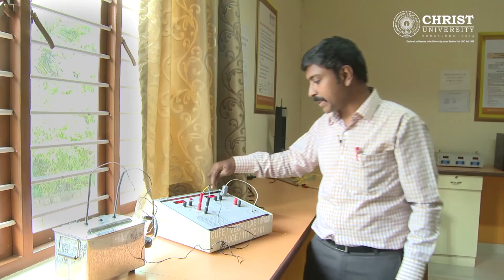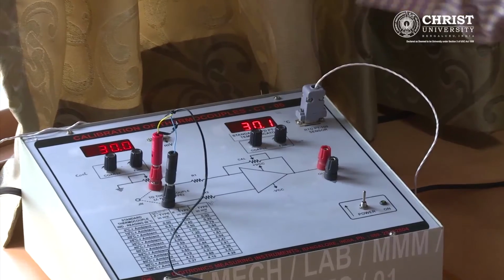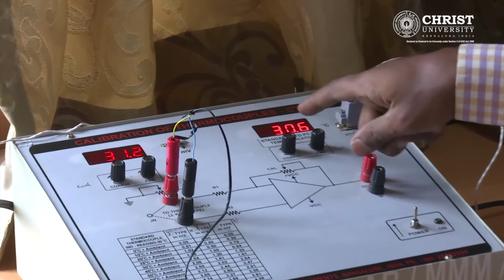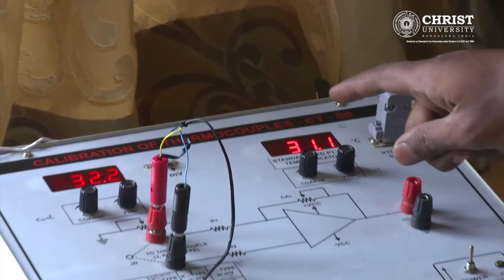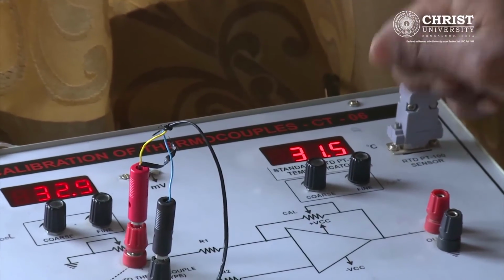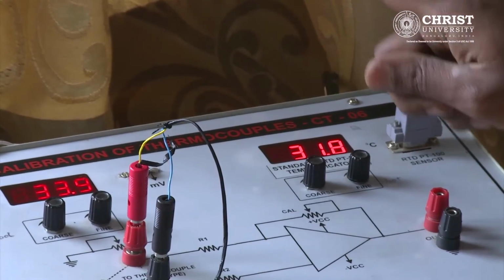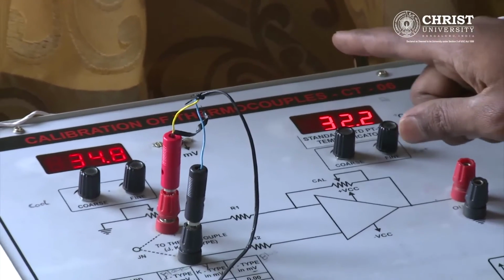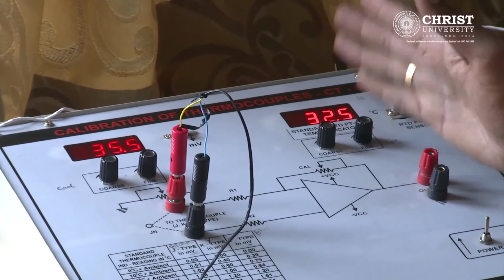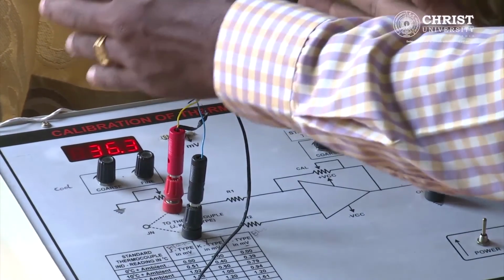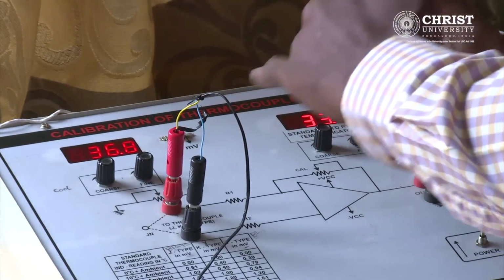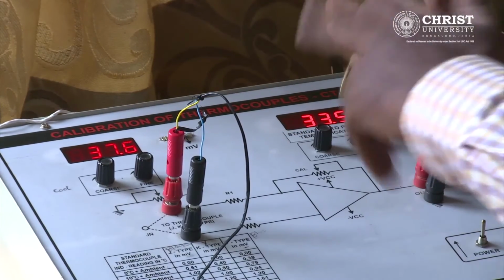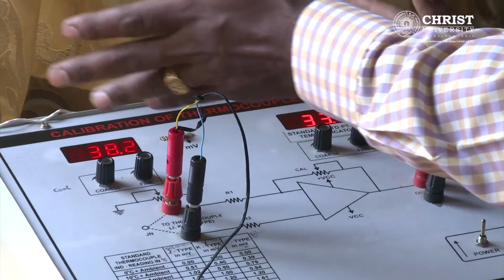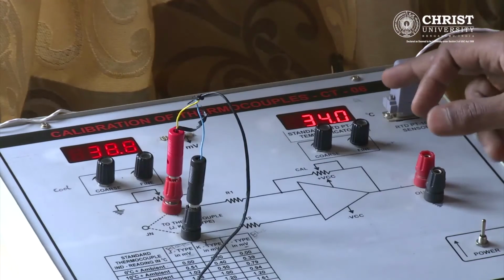If you see the display here, both displays have started moving now. We started with 28.6 from the right display. So we have to wait for another 10 degrees centigrade increase, so that should be 38.6. After it reaches 38.6, what is the corresponding value according to 38.6 of the RTD temperature? That will be the exact temperature of the thermocouple.